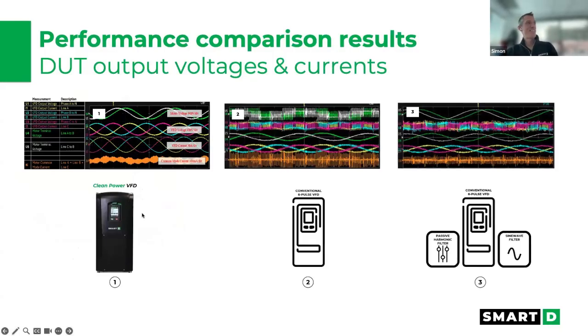So here you have it. If you really want to remove all of those harmonics in the signal, you can see it here. The output of the clean power VFD is pure sine waves, both in terms of voltage and in terms of current. With your typical drive, you can see clearly the PWM in terms of voltage, and you can see how your signal in current is a pseudo sine wave, but you have this choppiness because you can actually see the different pulses there. And to get the same kind of result, you really need to go to a sine wave filter.